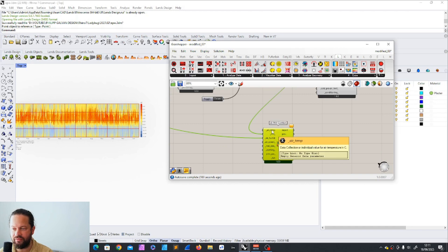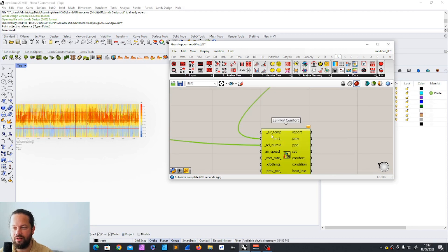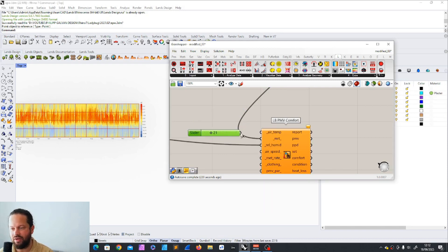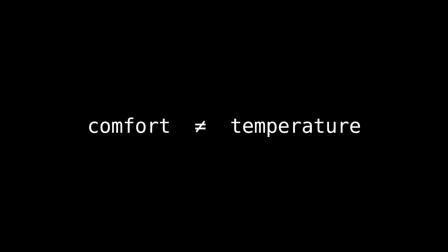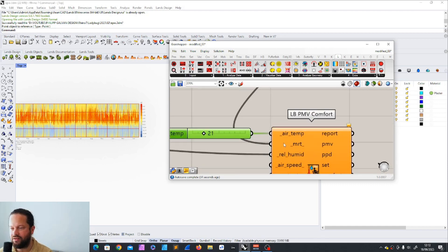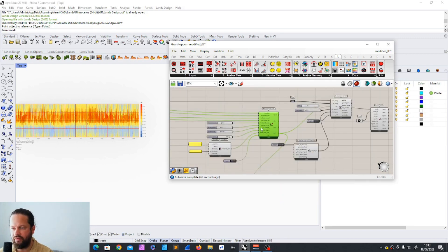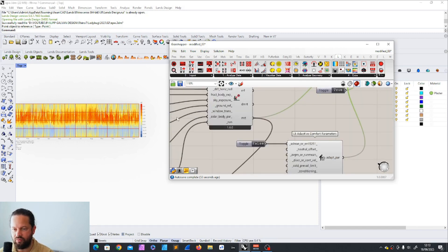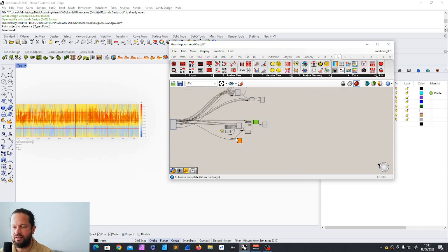What can we actually put in here? We have the air temperature — again, we don't know the air temperature indoors, that's tricky. Let's say I assume a building with a very efficient cooling and heating system that keeps the temperature always between 21 and 23 degrees. Comfort is not just temperature; it equals temperature, humidity, and airspeed — and what you wear, how you move, whether you are seated, standing, or lying down. We also need the mean radiant temperature, which we already built for the adaptive model, and we can reuse that. We just take this output and place it in here. Watch the previous video — that's why.